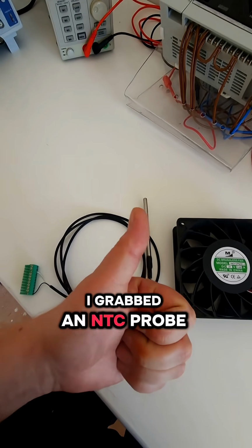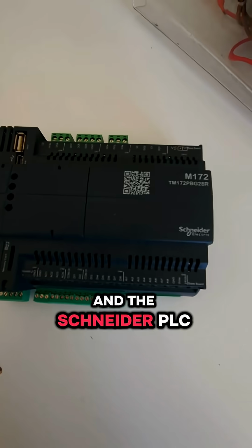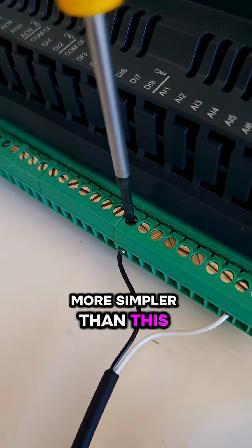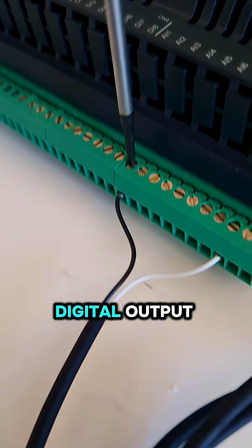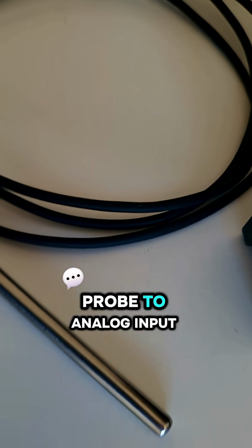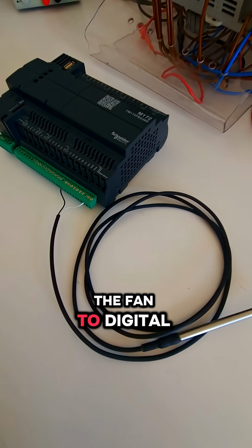So I grabbed an NTC probe, a fan and this Schneider PLC. It doesn't get much simpler than this: one analog input and one digital output. I wired the NTC probe to analog input 1 and the fan to digital output 1.